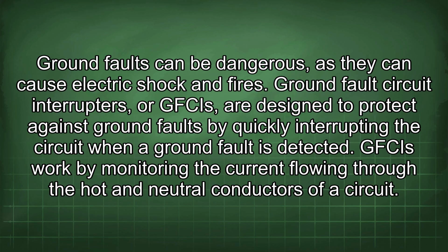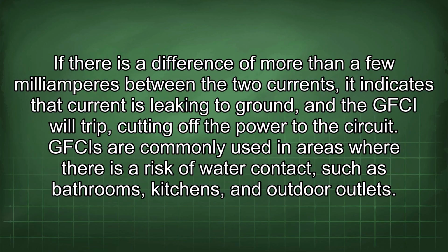Ground fault circuit interrupters, or GFCIs, are designed to protect against ground faults by quickly interrupting the circuit when a ground fault is detected. GFCIs work by monitoring the current flowing through the hot and neutral conductors of a circuit. If there is a difference of more than a few milliamperes between the two currents, it indicates that current is leaking to ground, and the GFCI will trip, cutting off the power to the circuit.